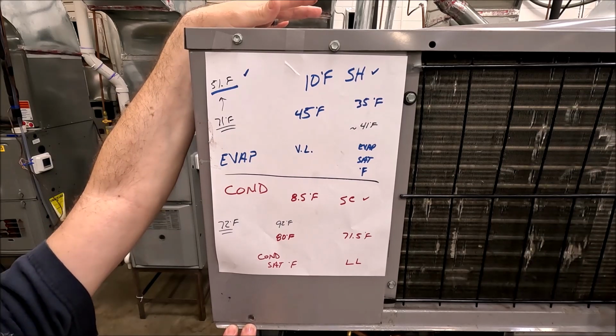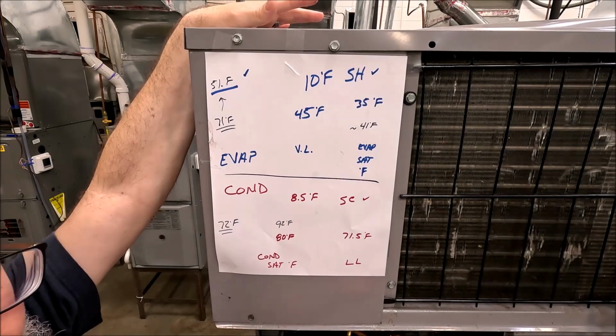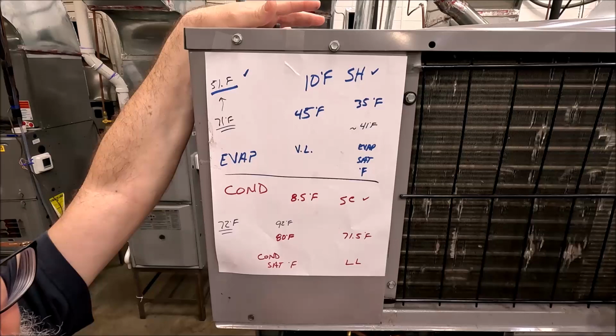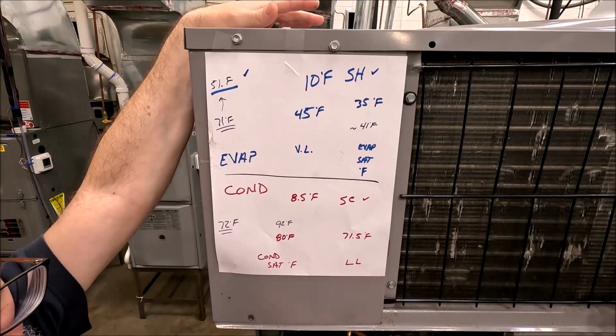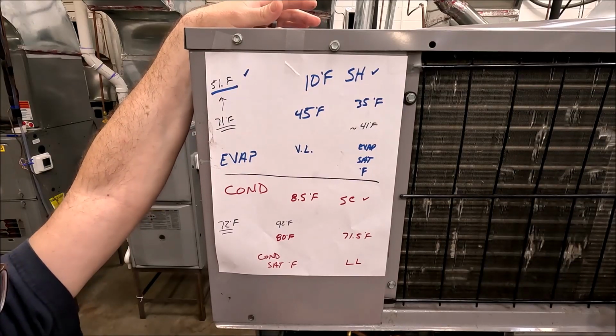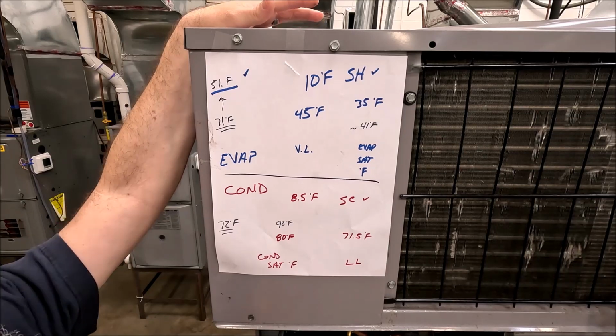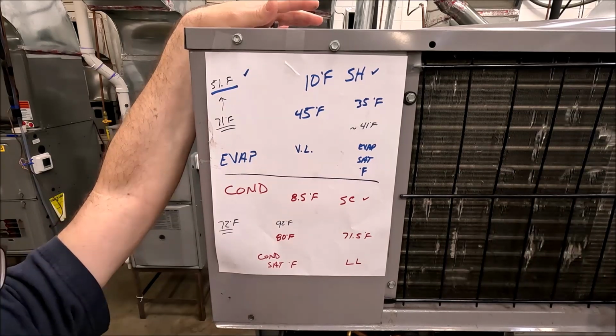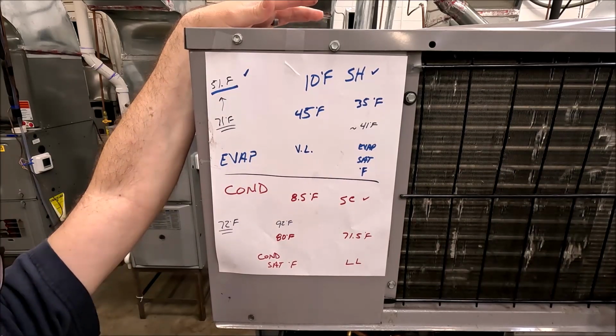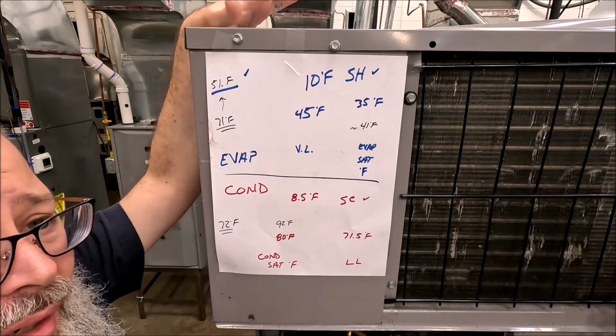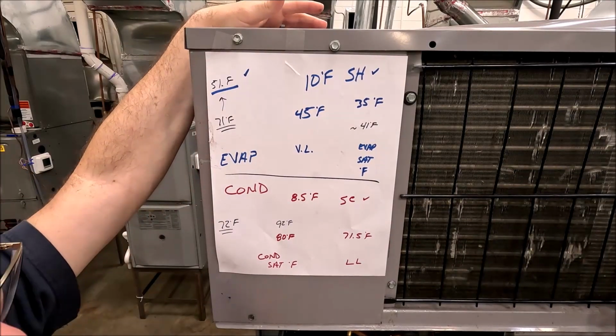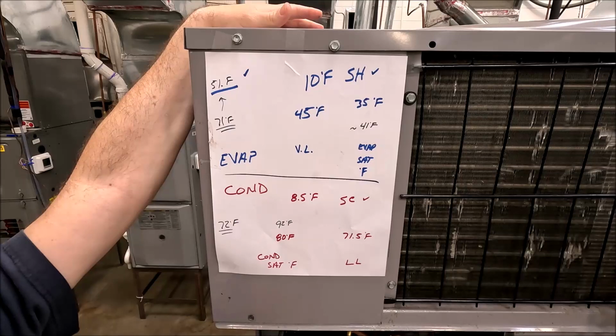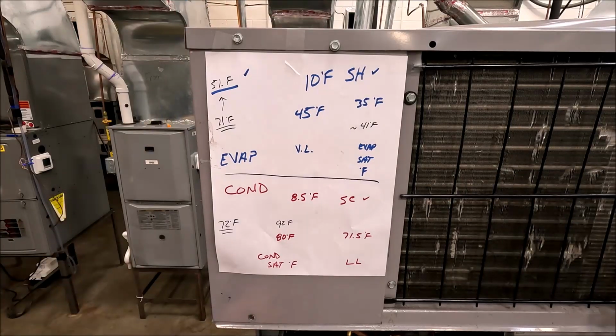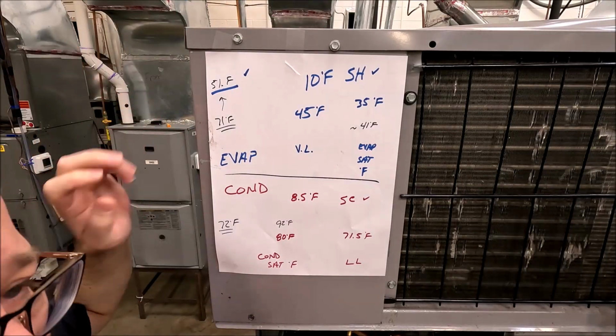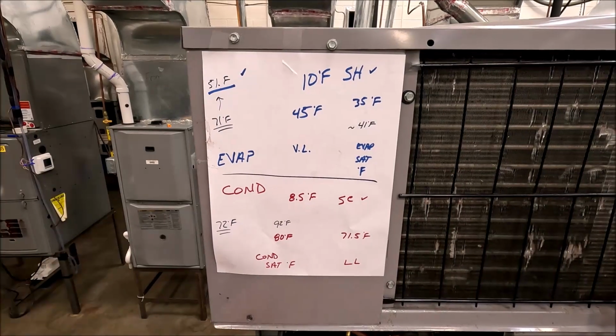Sometimes you get a call back. Sometimes, especially if you're there for a cleaning, if everything's been working right, you're just there to do a filter change and some coil maintenance and stuff like that, you probably don't have much to worry about. If you're there because it was a problem, and you don't find anything electrical, then yeah, you've got to do some digging. Maybe there's an intermittent problem somewhere. But my big thing for right now, do your numbers. Time will get you there.